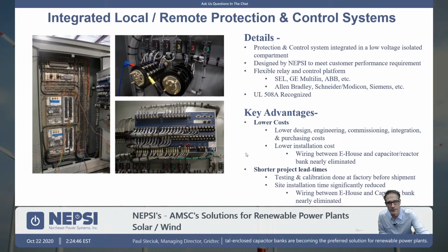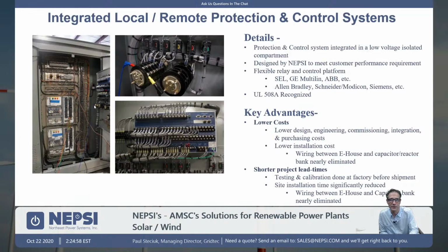e-house. And you can see here on the left, this customer had chosen to put all of the protection and control into our cabinet. And what that does is it eliminates all the costs associated with running the A and B contacts, the trip and close contacts, all the indicators, all this wiring that would exist between the main capacitor bank and the switching devices and the current transformers and so forth are brought back into the e-house, and there's a significant amount of site costs associated with that.